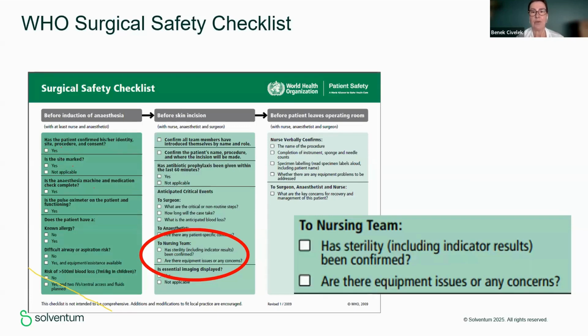Of course, chemical indicators alone will not tell about sterility because we also need the response from the biological indicator. As I told in the beginning, all these monitoring levels support each other. So if the chemical indicator is a pass, we also have to get confirmation from the biological indicator.